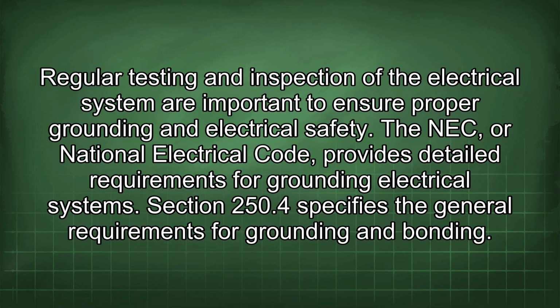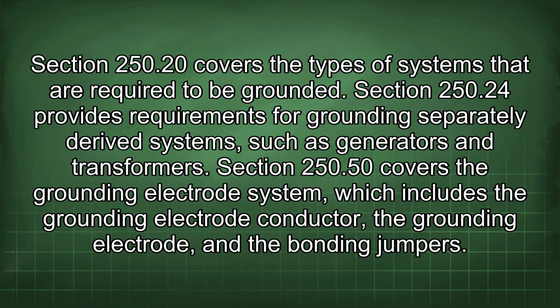The NEC, or National Electrical Code, provides detailed requirements for grounding electrical systems. Section 250.4 specifies the general requirements for grounding and bonding. Section 250.20 covers the types of systems that are required to be grounded. Section 250.24 provides requirements for grounding separately derived systems such as generators and transformers. Section 250.50 covers the grounding electrode system, which includes the grounding electrode conductor, the grounding electrode, and the bonding jumpers.